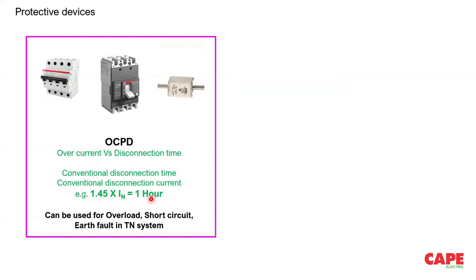Probably it may offer much faster disconnection, but the circuit has to be designed in such a way that up to this much time, your circuit shall withstand that overcurrent. The device which is having an overcurrent must be able to withstand this much time and this much current. These devices can be used for overload, short circuit, and earth fault in TN system. Please note that the effectiveness of automatic disconnection of supply as a fault protective measure means against earth fault. We are talking about the last one, earth fault in TN system. You can have an OCPD for disconnection.